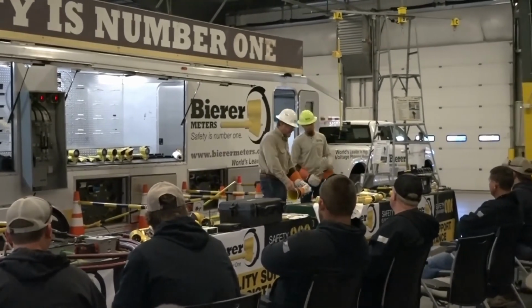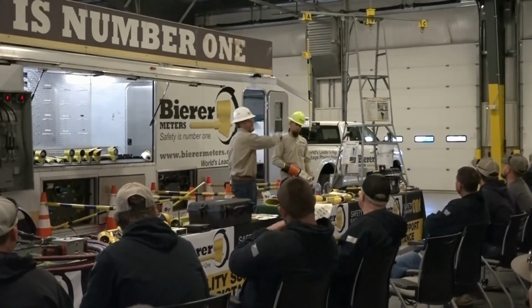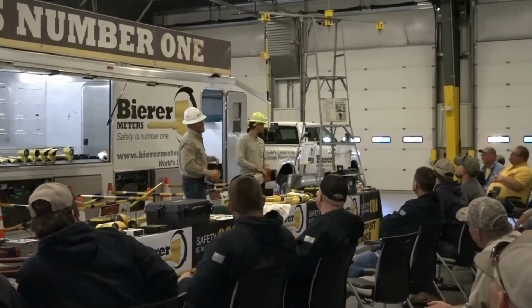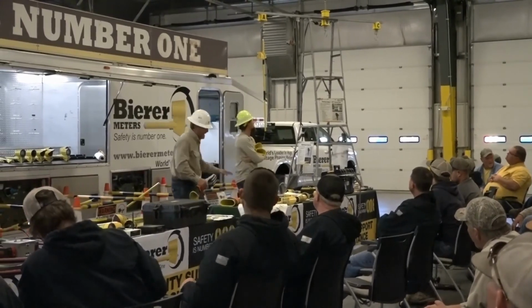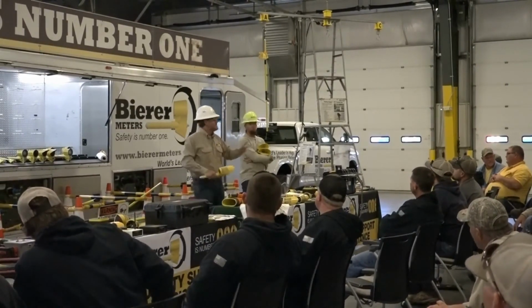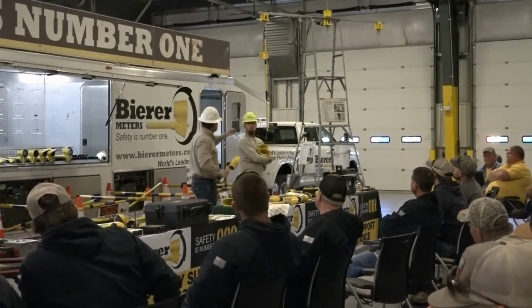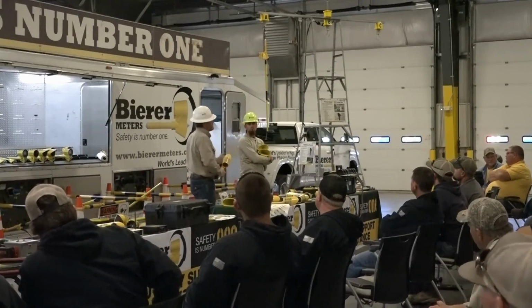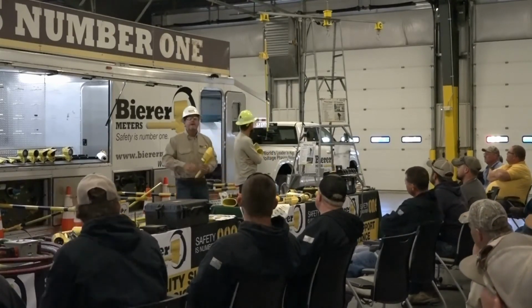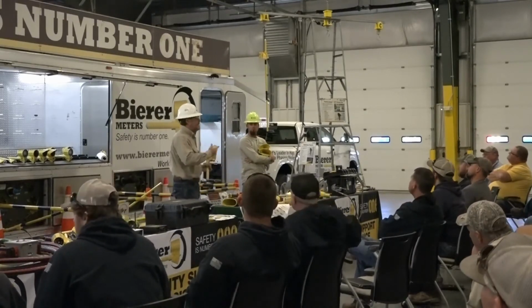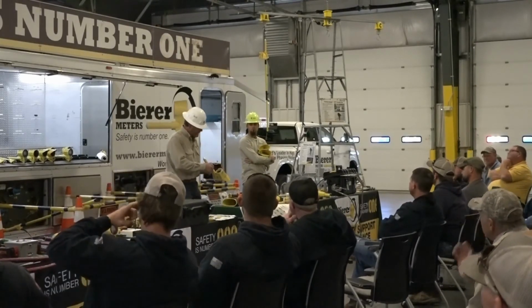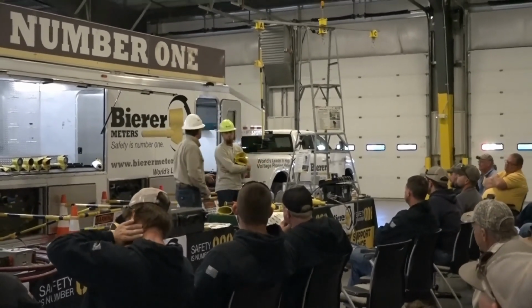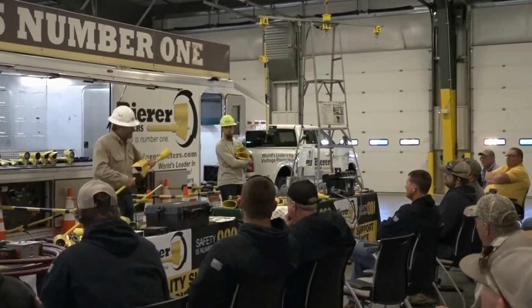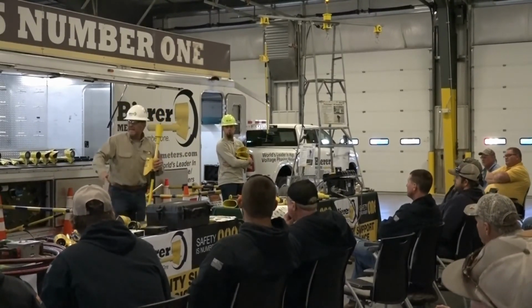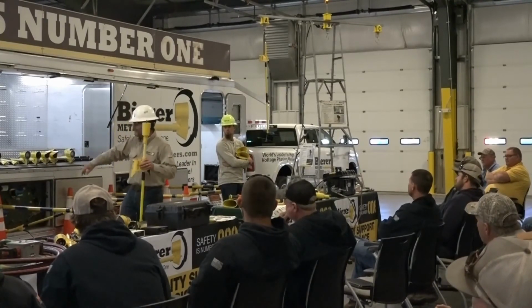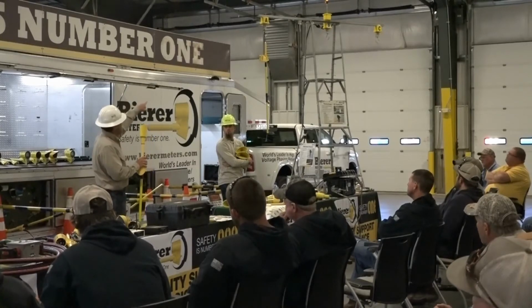So what we're going to do is we've got some overhead up here, 7200, and we got a PD800W reference probe. That's the reference probe, it doesn't have the sun shield on it, so you know that's the reference probe. If it's energized, we turn the reference probe on, and we place it and hang it on that conductor. A white light comes on, hot or not, then we know that conductor is energized. All right, and then Dylan's going to use the PD800W meter probe right here, and he's going to check out our conductors one after another. We're going to be on an A phase.